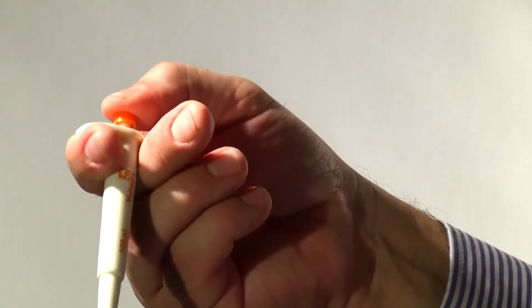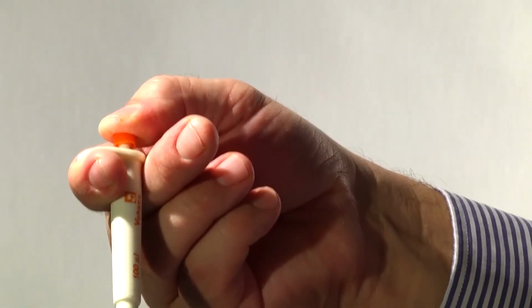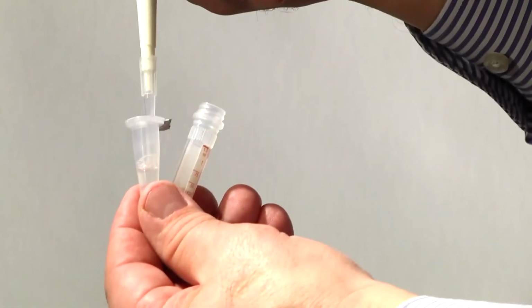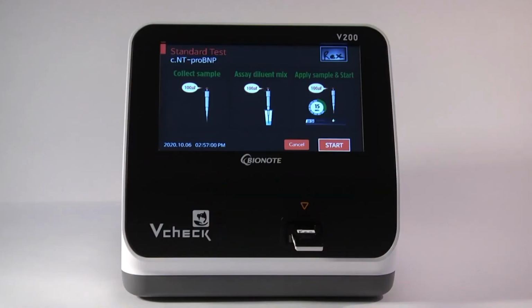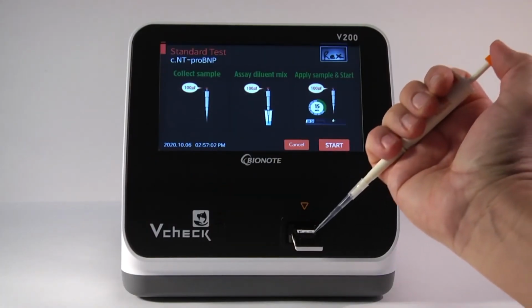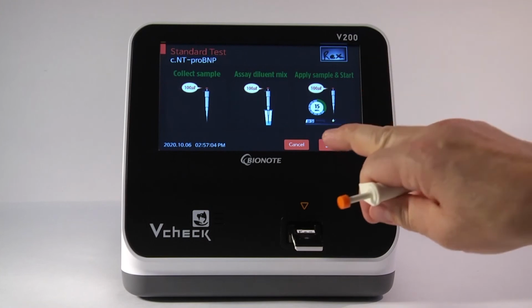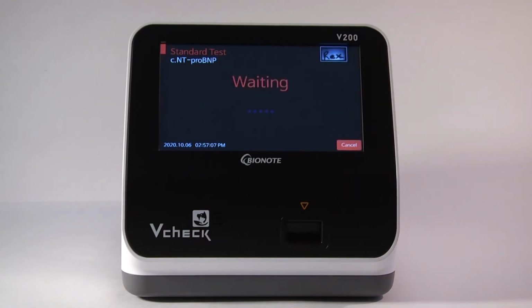Once you mix it 6 to 8 times, press the 100 microliter pipette to get the sample mix, draw your sample, and put it into the device. Tap Start immediately. It is important to tap Start immediately because each device has a built-in quality control, as you can see with those 5 little circles. That's the internal QC running on the device. If you add the sample outside of the unit, it will not run the quality control test, and it will display a contaminated error message.